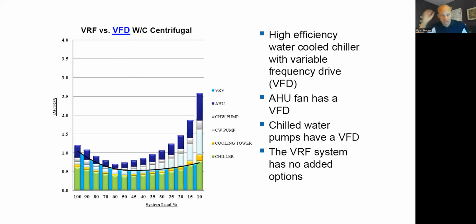When you do compare these, like I said, you have to do an energy model. You can't just say, oh, this one's got this EER and that one got that EER. No, because on VRF, it includes all energy, meaning all fan and distribution energy. On chillers, it does not include pumping distribution energy or fan energy. So it's not a fair comparison. You got to compare it all. This was an example comparing it all.